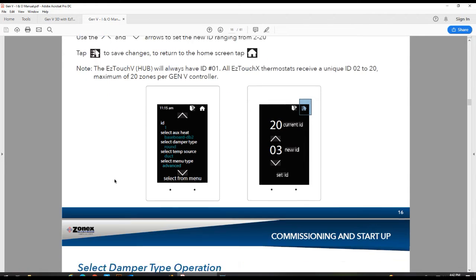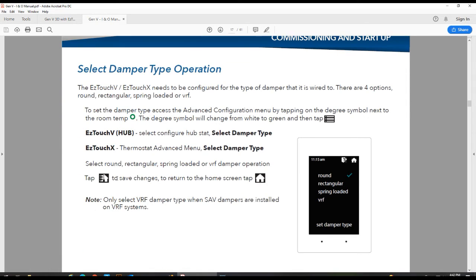Once you've set all your IDs, the next step is we want to confirm our damper operation or type. After you set the ID, when you go back, you'll want to select your damper type. Each thermostat can control a number of different dampers, so round or rectangular. These round and rectangular dampers are power open, power closed dampers, and the thermostat will modulate those dampers accordingly. If you have a system that is 5 tons or less, you can use a spring-loaded damper. And if you're utilizing a VRF system with our SAV or smart air valve dampers, then you'd want to configure the thermostat for VRF. So go ahead and set your thermostats for the proper damper operation that you have installed and that it is going to be controlling.